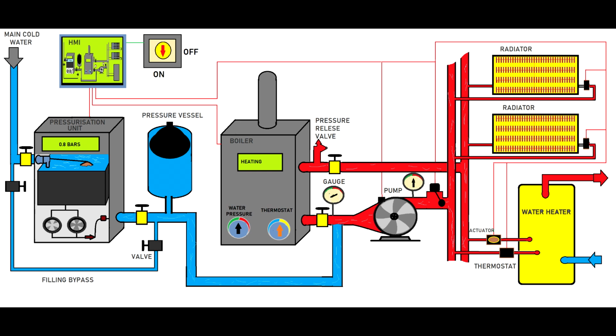Going further, if you remember, we talked about the heating system, how the heating system works, and how they control it and so on. Now, as you will see here on this heating system, you have a pressurization unit, you have a pump, and you have the boiler. Now all these 3 should normally be correctly integrated into this programmable logic controller or building management control or any other form of control you are using. If you're not doing this and you have a central monitoring system somewhere, you might send the wrong technicians, because sometimes you have to send either an electrician or a gas engineer or a refrigeration engineer, an air conditioning engineer, I'm sorry.